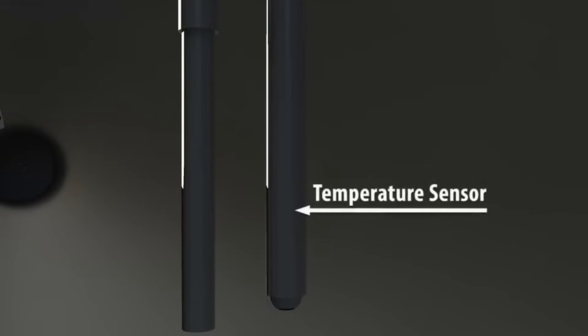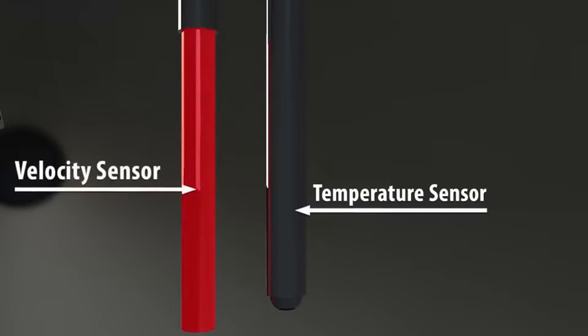So, how does this amazing technology work? In this cutaway view of a typical pipe, the sensor probe is inserted into the center line of the flow. Thermal flow meters have two sensors immersed into the flow stream. One is a temperature sensor, which measures the actual gas temperature inside the pipe as a reference, regardless of the flow velocity. The other is a heated sensor, called the velocity sensor, illustrated here in red.